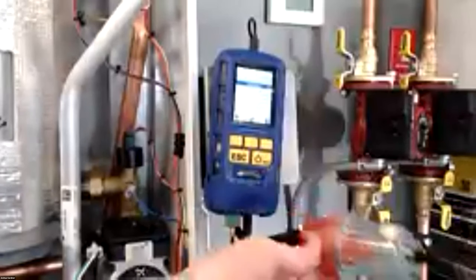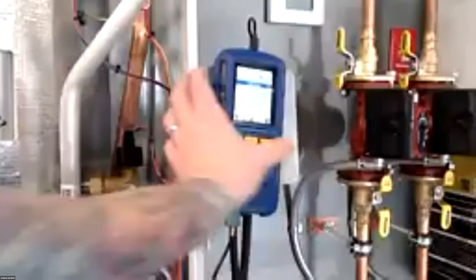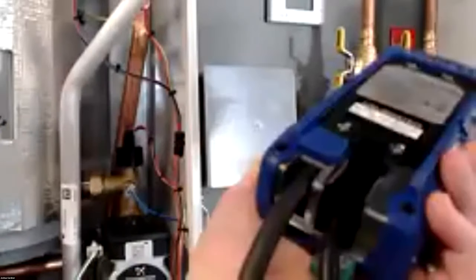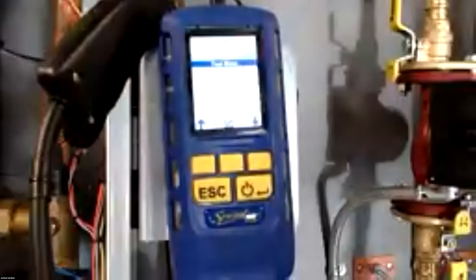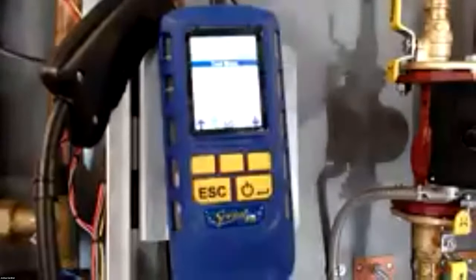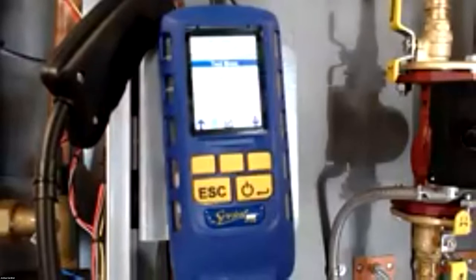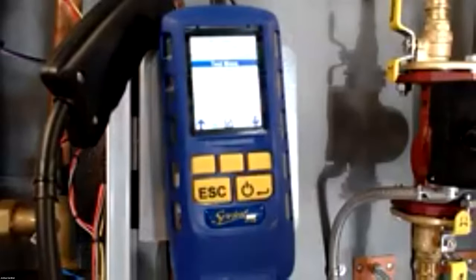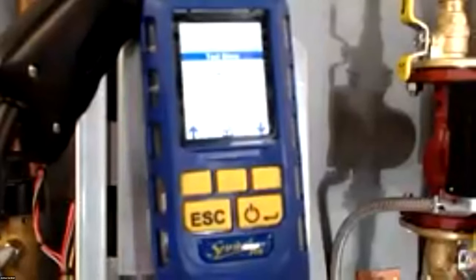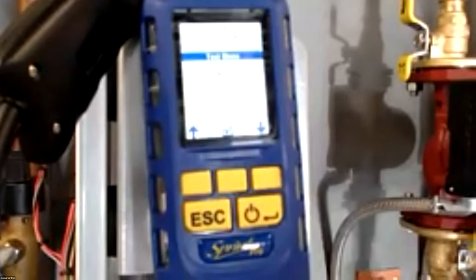Condensate trap. I think a few manufacturers use this type of condensate trap. There's a little filter in there. And on the bottom, you have your temperature probe. You can use another temperature probe if you want to do intake air temperature. You have positive and negative pressure ports, and then the connection for the analyzer. Magnets in the back. And so our rep agency, J&K Sales here, has this analyzer, and they gave this one to me for free, to be all honest. And they market it. It's made out of the same plastic material as motorcycle helmets. So they take these analyzers when they're doing trainings and sales pitches, and they just throw them on the ground. And they work awesome. So they're very, very rugged. Comes with a printer, depending on which model you buy. I think they're priced under $1,000, all right, with all these features, which is really nice.